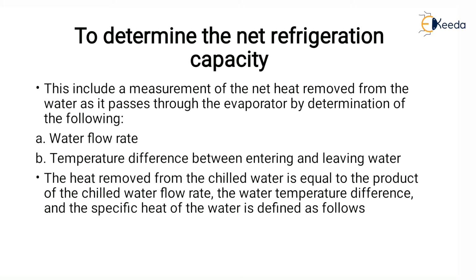So the first test is to determine the net refrigeration capacity. This includes a measurement of net heat removed from the water as it passes through the evaporator, by determination of first the water flow rate and second the temperature difference between the entering and leaving water. The heat removed from the chilled water is equal to the product of the chilled water flow rate, the water temperature difference and the specific heat of the water, and is defined as follows.